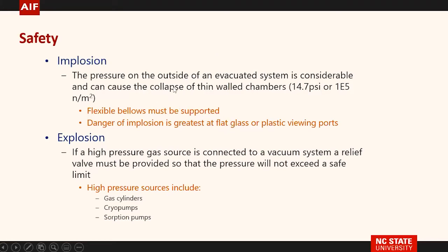There's really pretty little risk on that because the materials used are very strong. You have a bigger risk here, and that's from your gas cylinders. And in this course, we'll actually show you removing a regulator from a gas cylinder in a safe means. Your cryopumps, your sorption pumps also have some risk because cryopumps have like 300 PSI pressure in those lines.